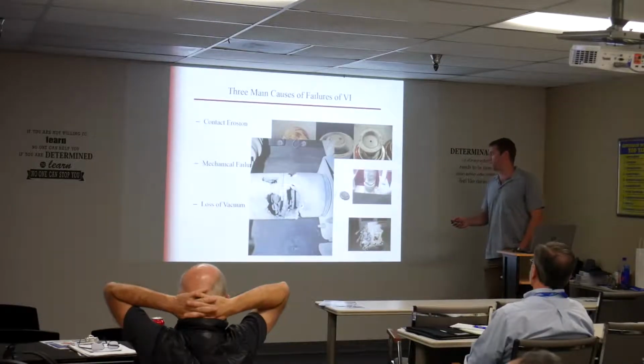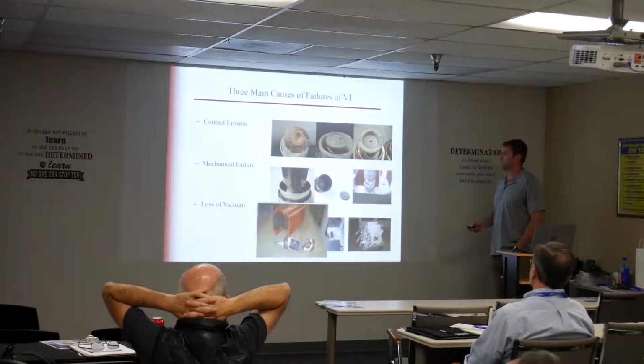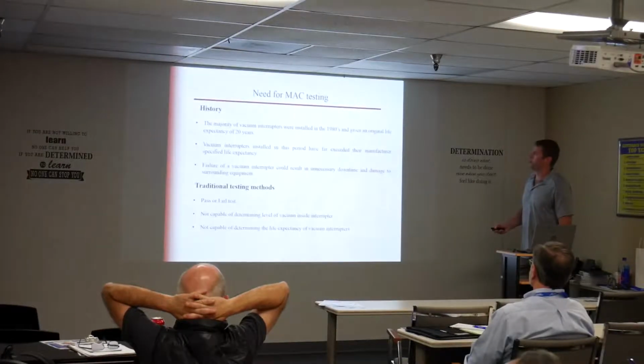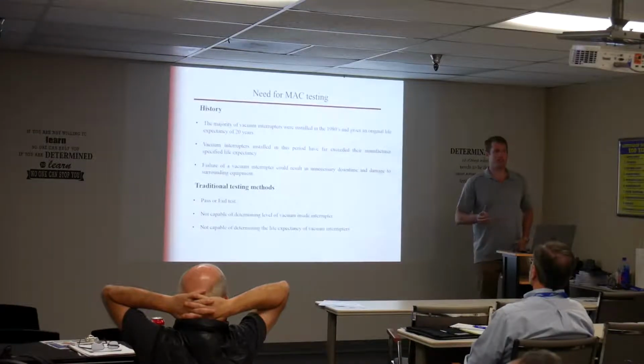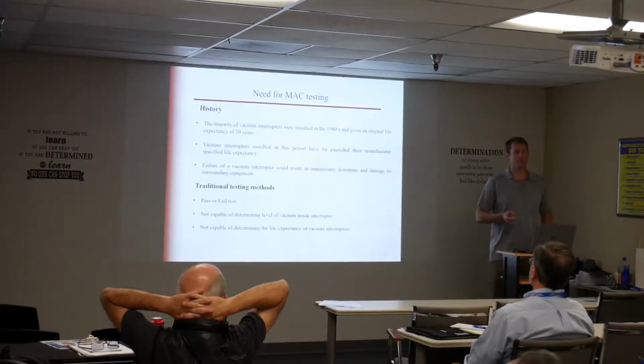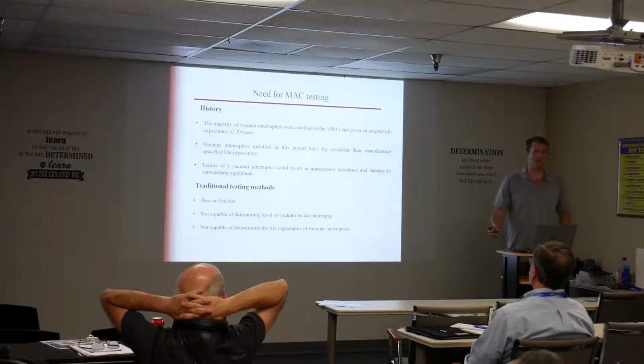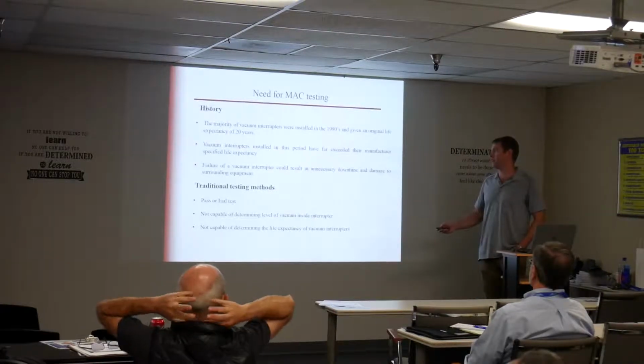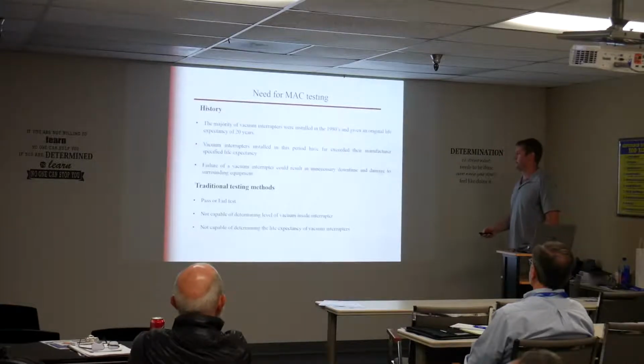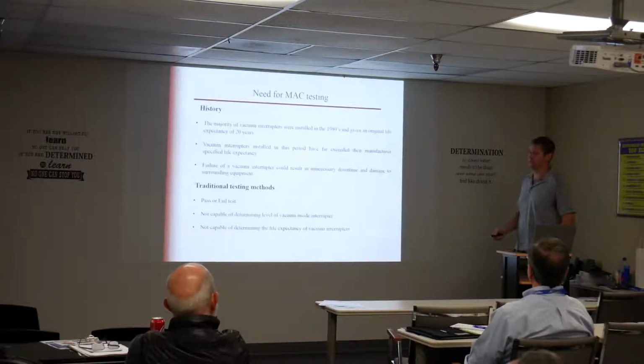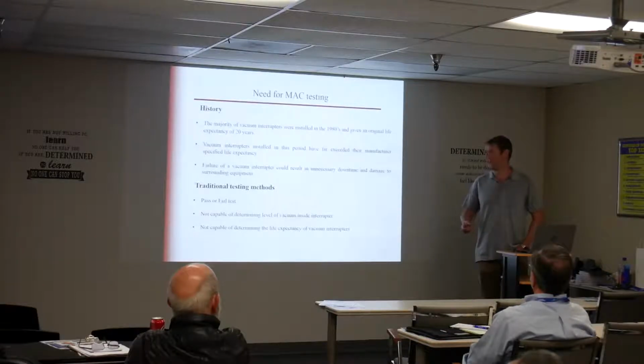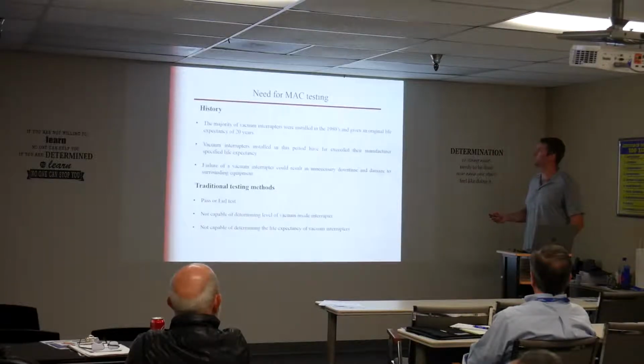And this was, before our field magnetron test set, there was just the AC or DC vacuum integrity test, which is simply go, no go, does it have a vacuum today or does it not? You're not capable of determining the level of vacuum, not capable of determining the life expectancy. It's either good or bad. You have no idea really what's going on inside that interrupter.